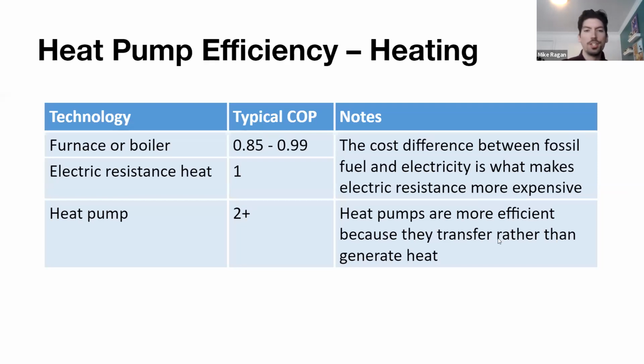So here's a chart just breaking down what a COP looks like for various different types of systems. And as said previously, electric resistance heat is a COP of approximately 1. It's going to be a little bit less than 1 because of those losses. Your gas-fired furnace or gas-fired boiler is going to see a COP of 0.85 to 0.99. If you have a 95% efficient gas boiler, that's what that is talking about in terms of efficiency. It's COP. So it's going to be burning a certain amount of gas or oil or whatever your fossil fuel driven heat source is, and you're going to be getting out a little bit less than that just because of losses in the system. With a heat pump, you're actually able to achieve COPs over 2, in fact, oftentimes throughout the year, greater than 3 or even approaching 4.